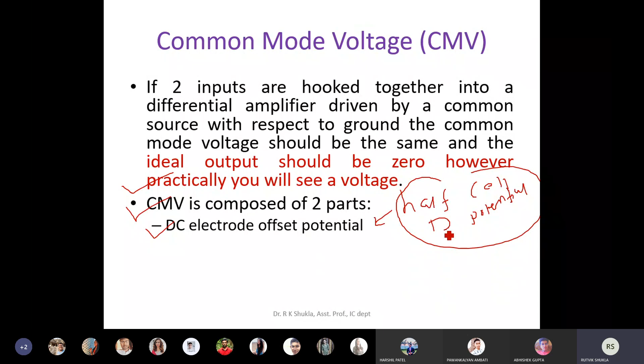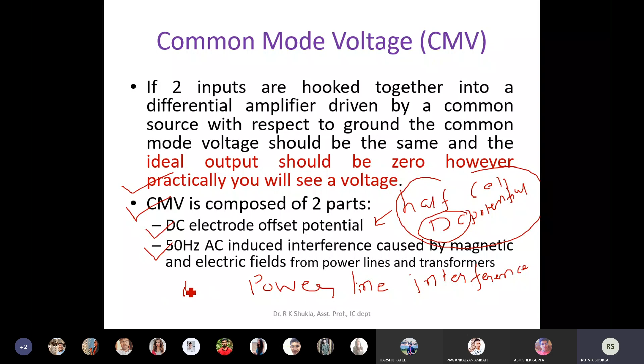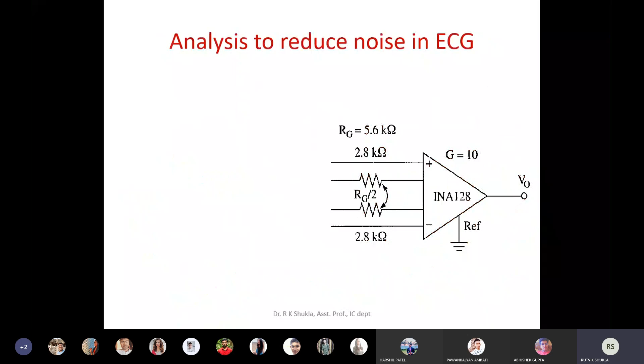The second part is 50 Hertz AC induced interference, which is caused by the magnetic and electric field from the power line and transformer. So this is nothing but your power line interference. These are two different types of noise. One is DC, which is due to the half cell potential of the electrode, and the second is the 50 Hertz induced noise, also called the power line interference. This noise is AC in nature. So two different types of common mode voltage are produced.